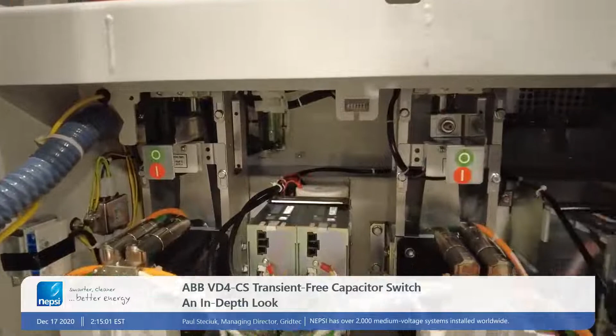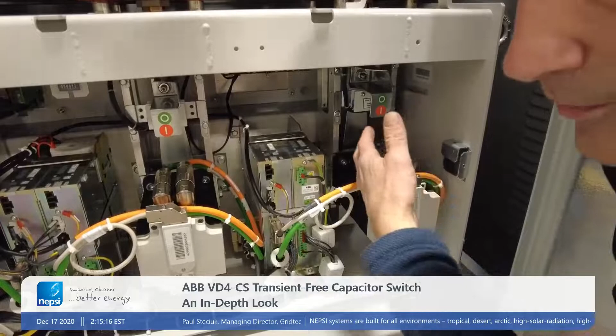On each of these poles, there's also an A and B contact located right at each pole, giving indication for that pole. Through the electrical diagrams, which Paul may go over in a bit, these three poles are brought out to terminal blocks, and also gang together to give the overall indication of whether the breaker is open or closed. So you can look at all three together or each individually. Incidentally, because it's point-on-wave switching, you need independent pole operation, otherwise you wouldn't be able to individually control each one.